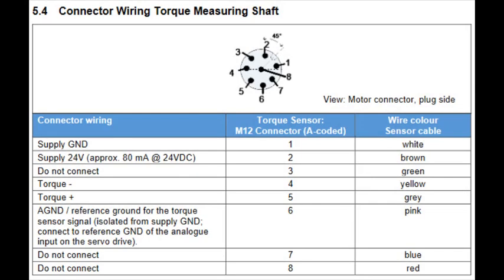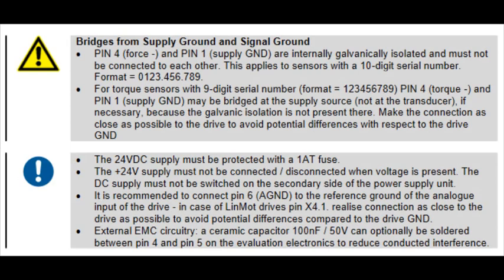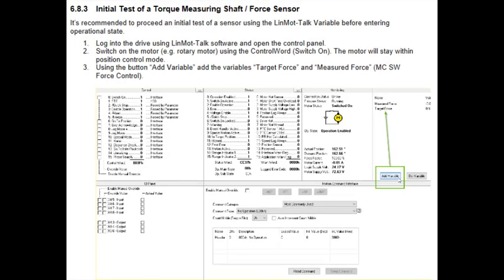As for this wire diagram, it shows where on the drive you will need to connect the pigtail side of the sensor cable, as well as what each wire of the pigtail end's purpose is. The 24 VDC supply must be protected with a one AT fuse and the +24V supply must not be connected or disconnected when voltage is present. This information can be found inside the PR02 linear rotary motor's installation guide along with tips and safety instructions.